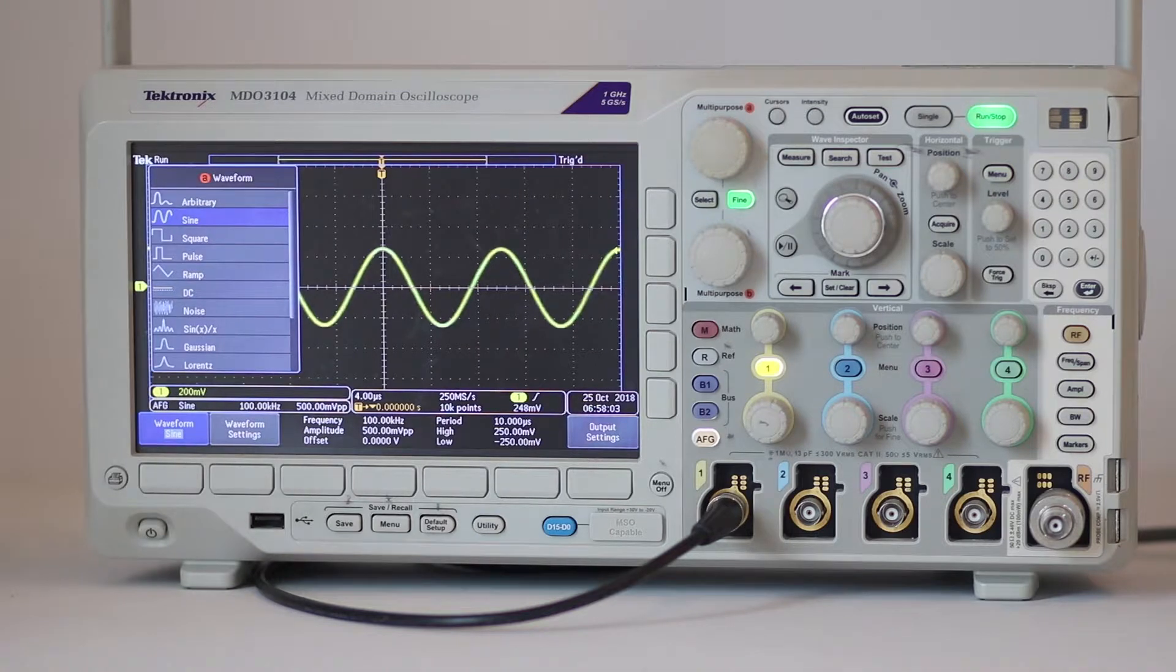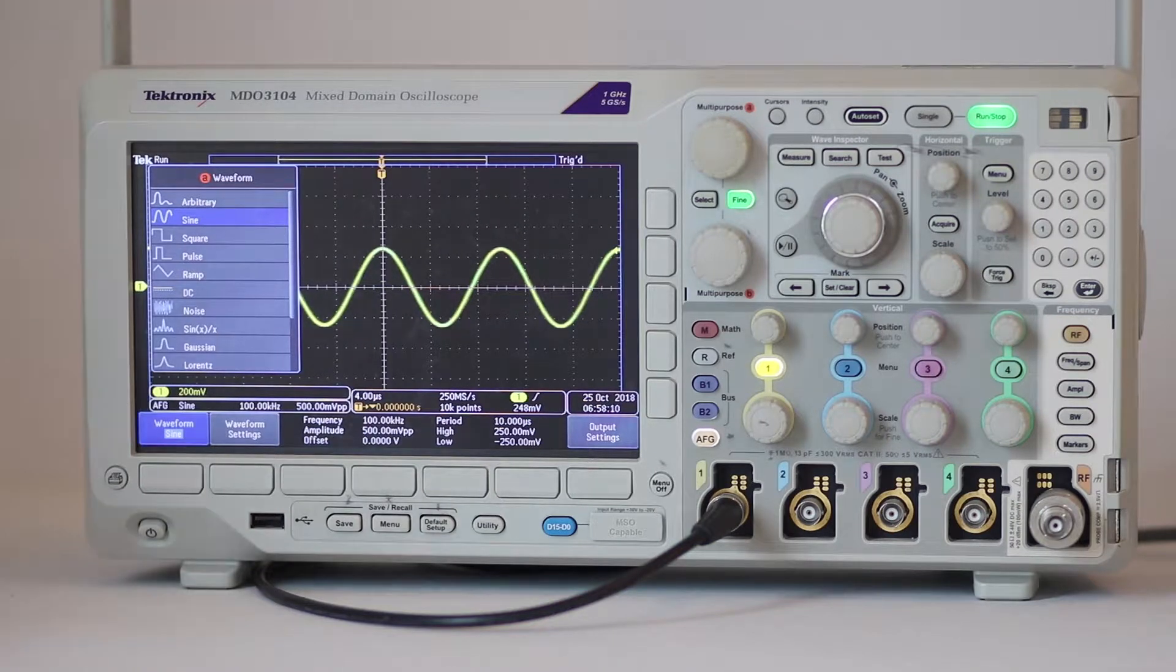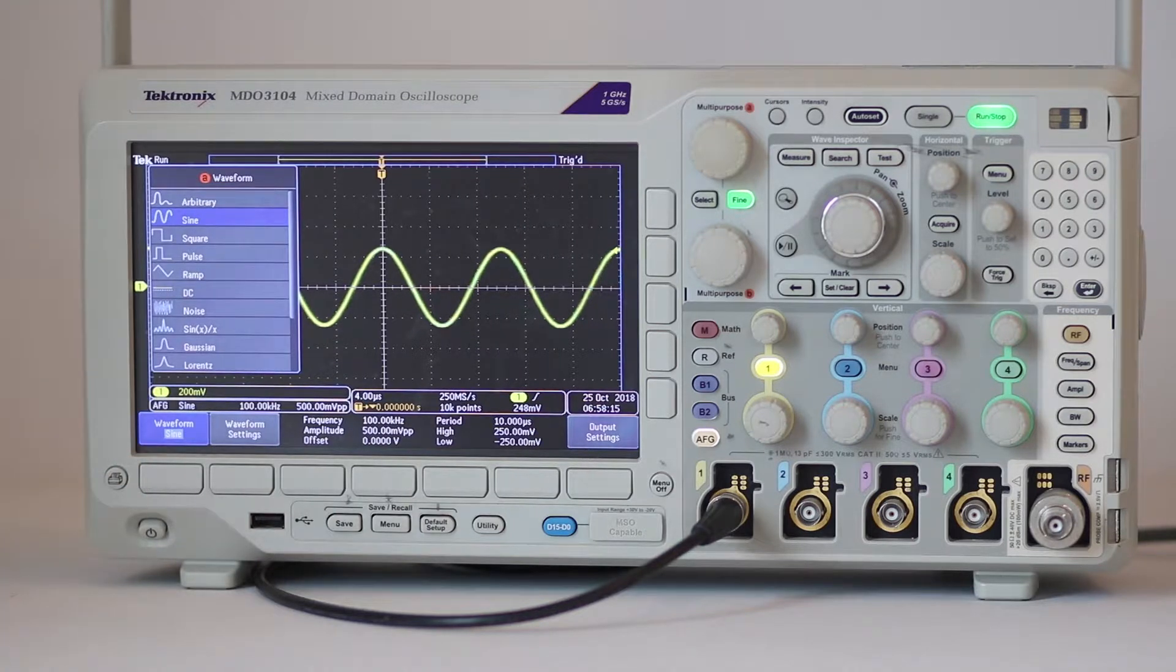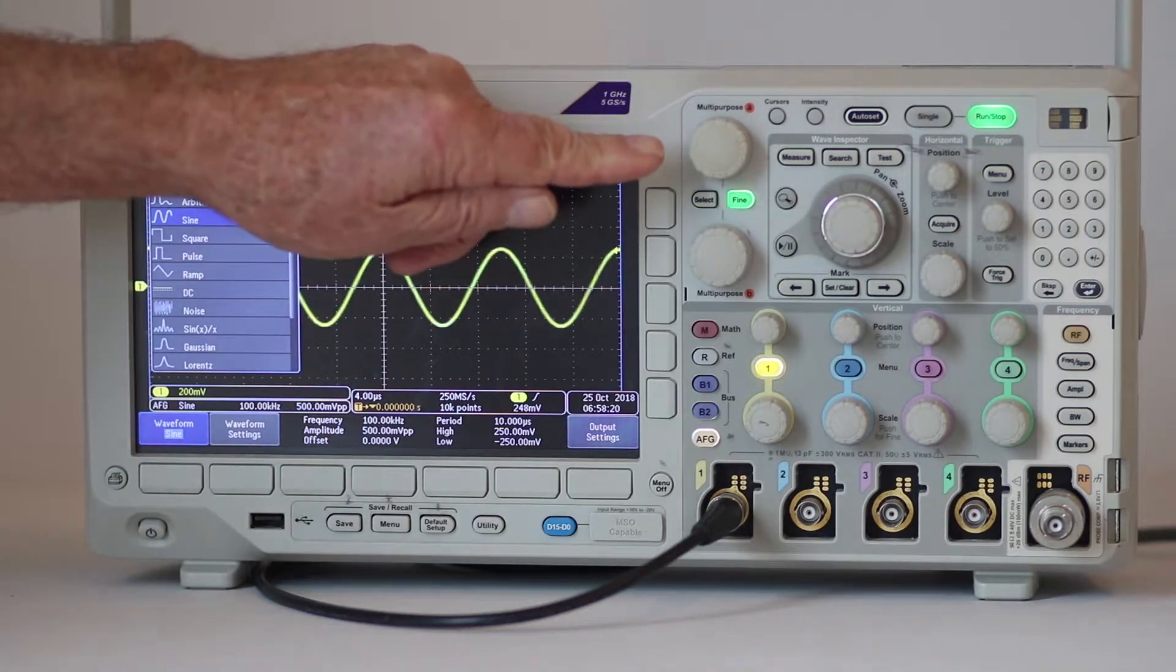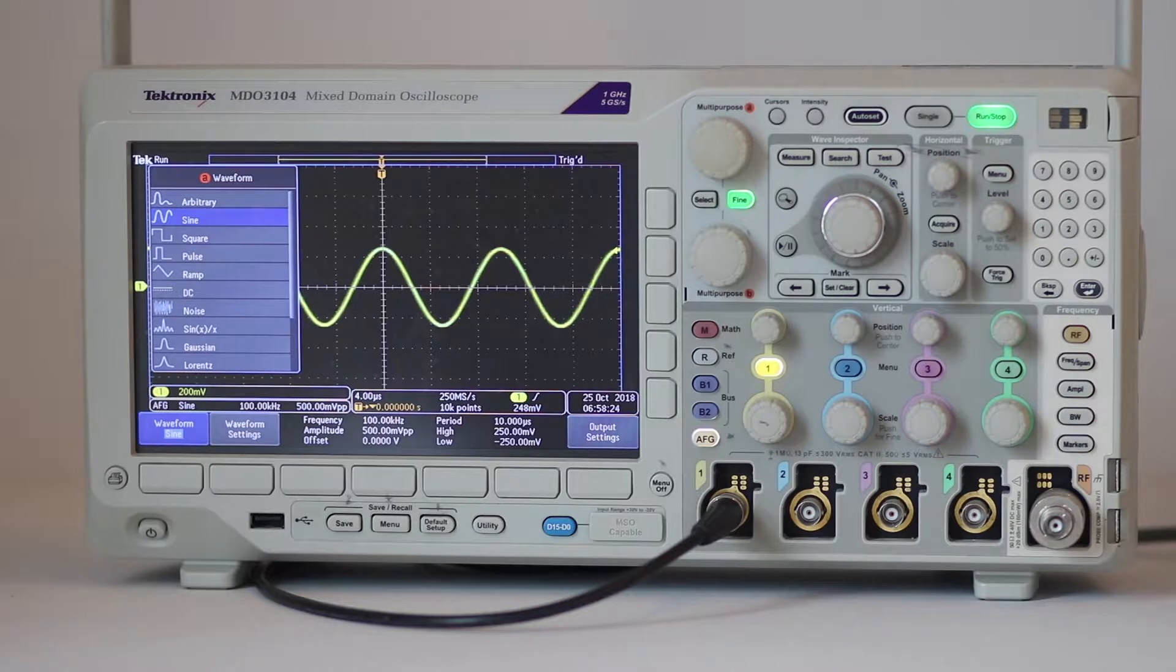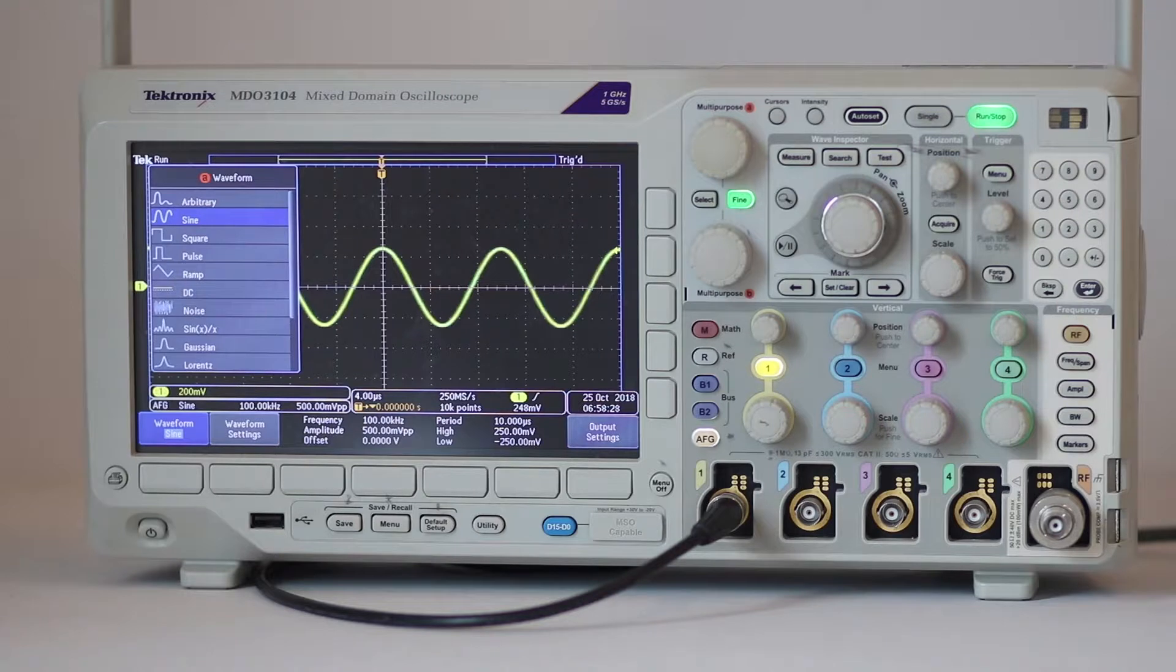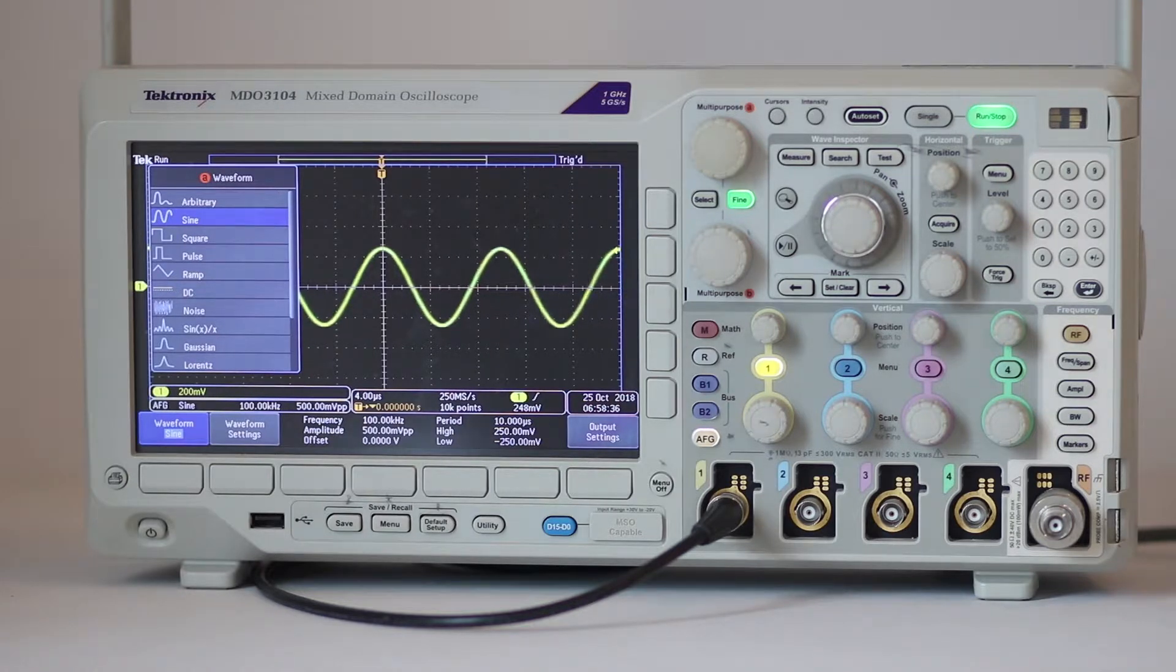The other waveforms can be accessed by pressing the soft key associated with waveform in the horizontal AFG menu. Then use multi-purpose knob A to scroll down through the available waveforms. Some of them, such as Lorentz, may require the user to press autoset to obtain a stable display. Then if you go back to sine you'll have to press autoset once again to restore the trigger setting.